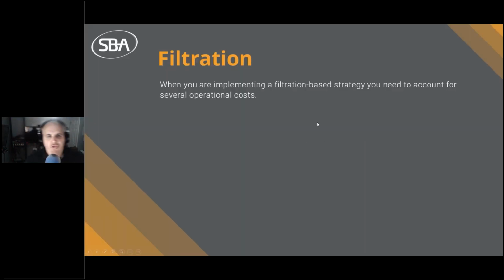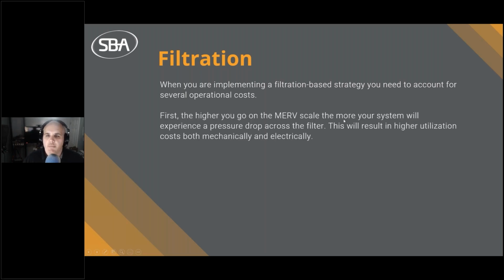Now, when you are implementing a filtration-based strategy, you need to account for several operational costs. I don't see people talking about this quite enough, in my opinion. First, the higher you go on the MERV scale, the more your system will experience a pressure drop across the filter. This is going to result in higher utilization costs, both mechanically and electrically. Remember, we're not just increasing our utility costs, but we're actually increasing the wear and tear on our equipment, and we are going to prematurely age our equipment. We're going to have to increase our PMs, our preventative maintenance tasks, to account for increased run hours.